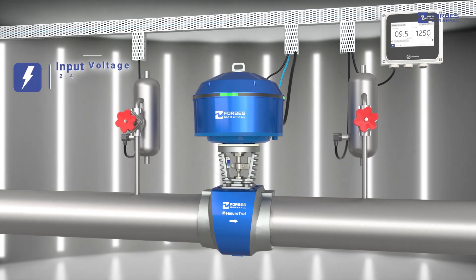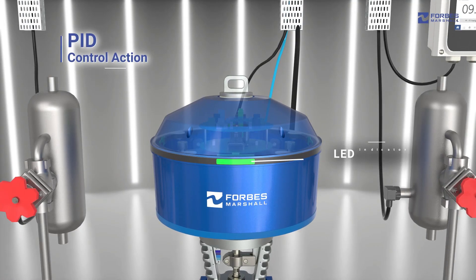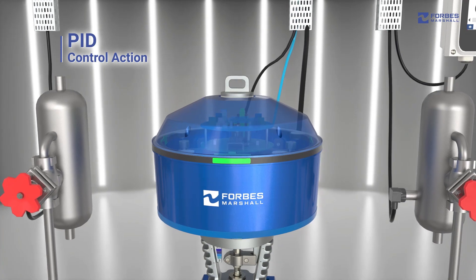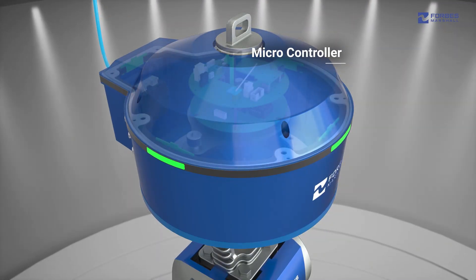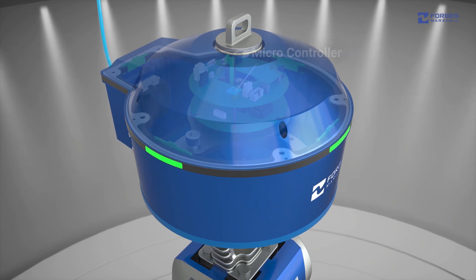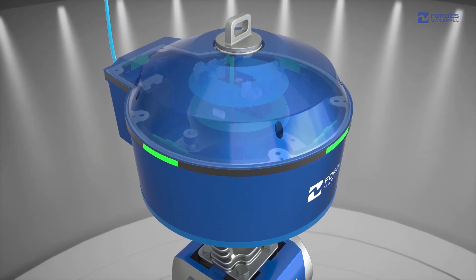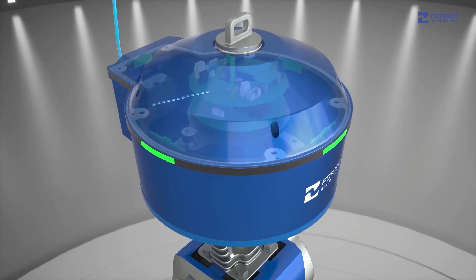Let's understand how MeasureTrol actually functions. The input voltage of MeasureTrol is 24 volts DC. Using an integrated PID control action, it monitors the actual process pressure against the set point via the use of external pressure transmitters. The microcontroller sends an electric signal to the transducer, which then converts it into an equivalent pneumatic signal. This enables the pilot valve to precisely control the pressure in case of any deviations.